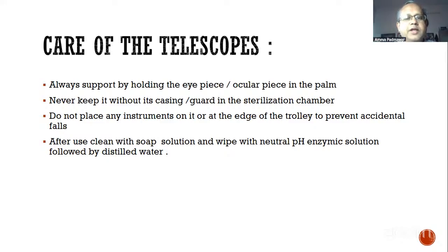So when you're carrying your scope over your trolley or taking it to clean or whatsoever, you have to always support it by its eyepiece. Eyepiece means the ocular piece where the camera gets connected to it. And never keep it without its casing, especially in the sterilization chamber, because when it gets sterilized, the impact of adjacent instruments on it can cause damage. The same thing carries when you keep it on your trolley. You should always keep it not covered by any other instrument.